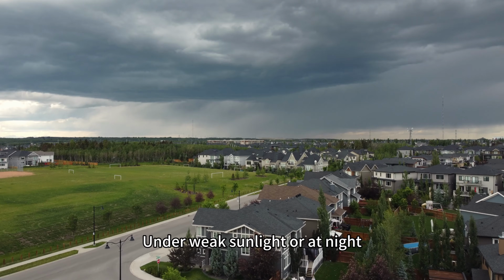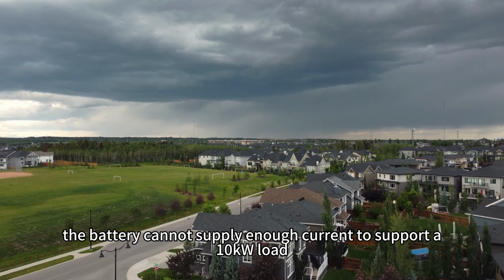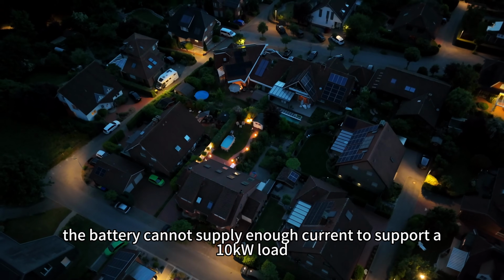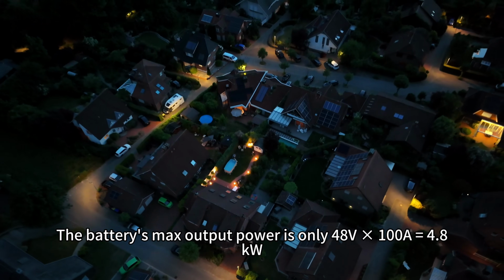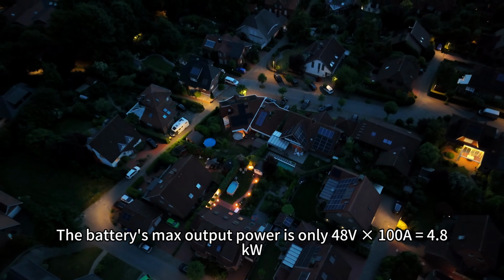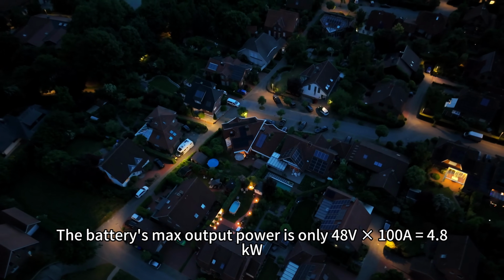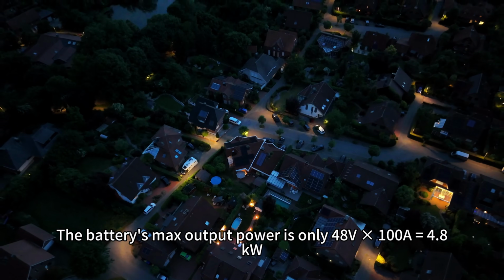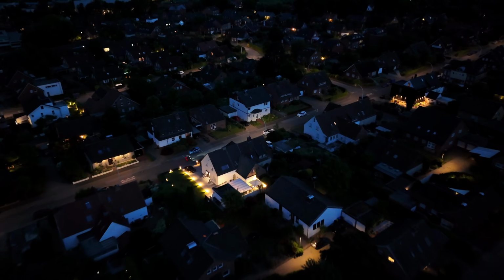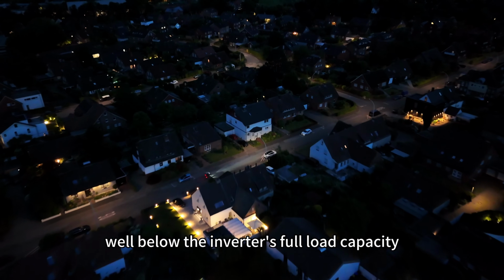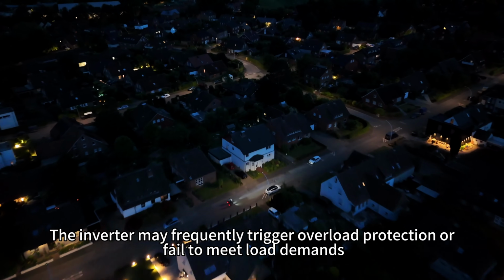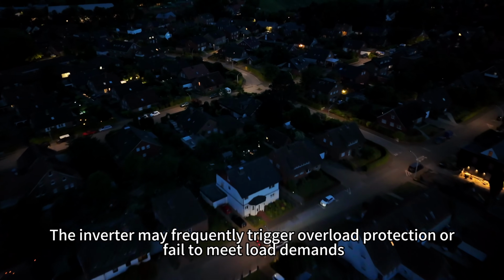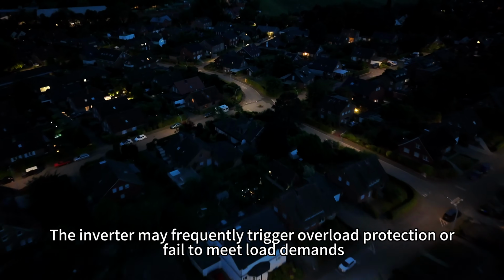Under weak sunlight or at night, the battery cannot supply enough current to support a 10 kW load. The battery's maximum output power is only 48 volts times 100 amperes equals 4.8 kW, well below the inverter's full load capacity. The inverter may frequently trigger overload protection or fail to match load demands.